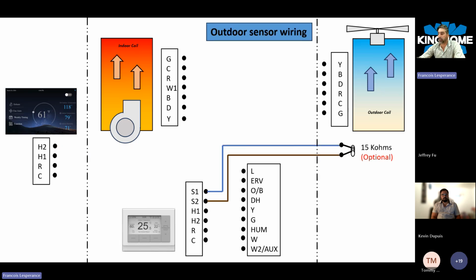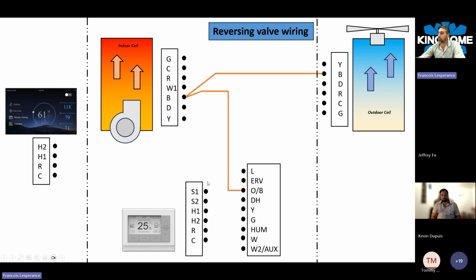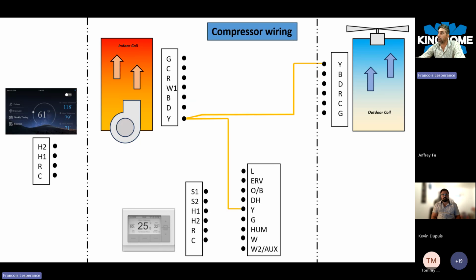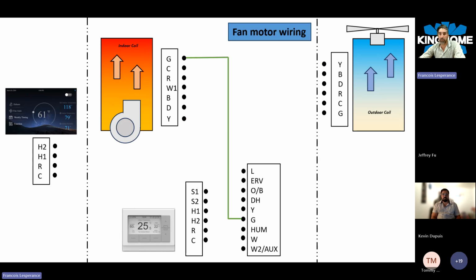Sometimes you may have some accessories as well. We can add an optional outdoor temperature sensor, 15 kiloohm, connected to S1, S2. We're going to use the reversing valve powered with the B terminal, in heating mode for our unit type. The Y terminal calls for the compressor to start. It could be directly on the board for a furnace, or for an air handler, it could be just a wire nut. The G terminal is straightforward, so it's pretty usual.